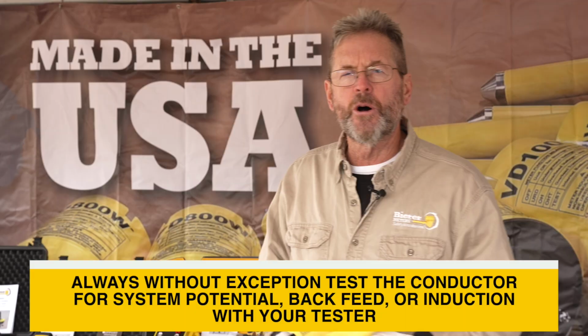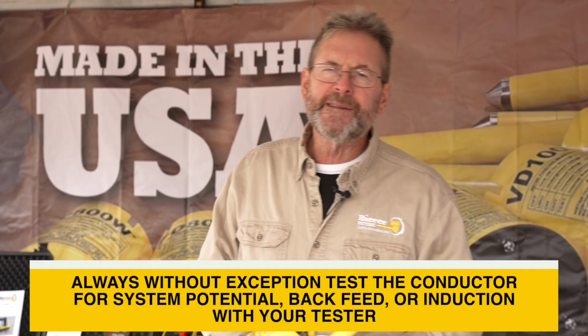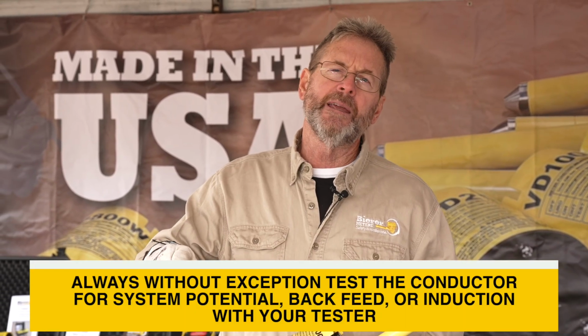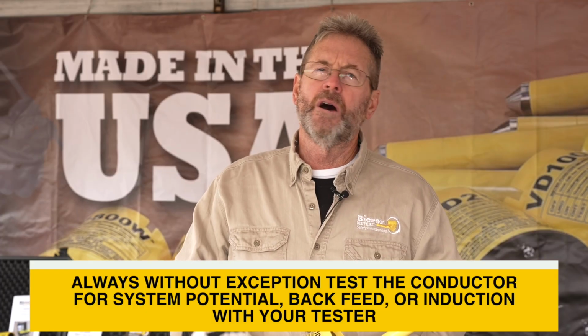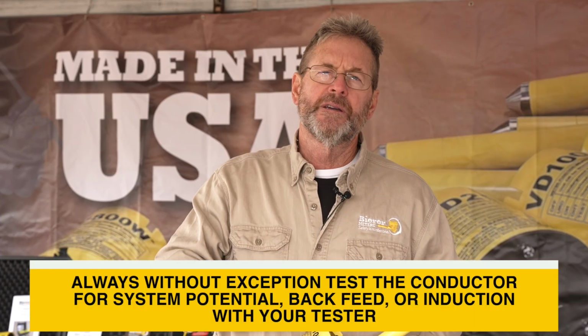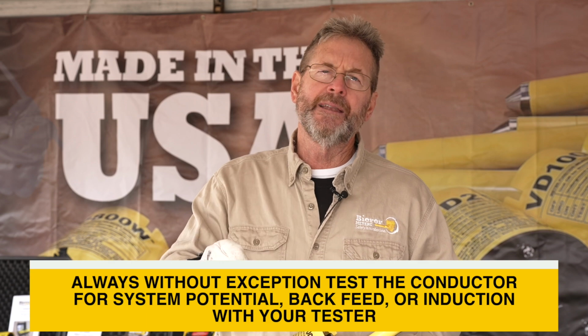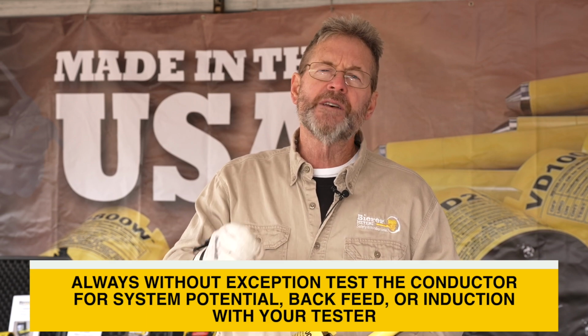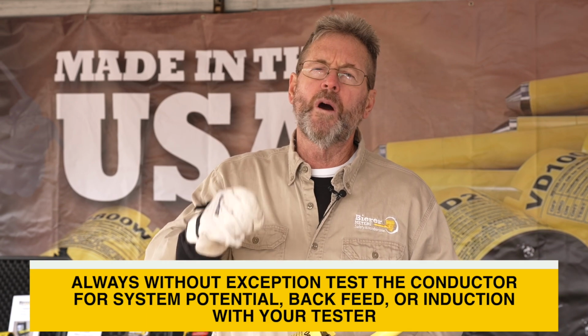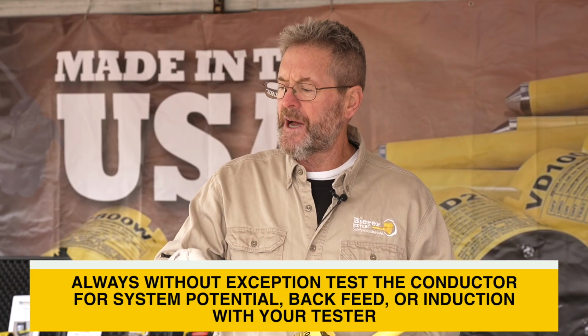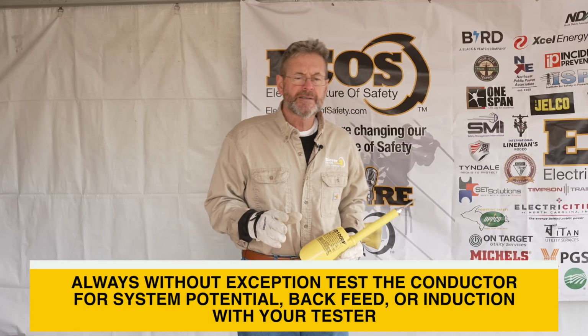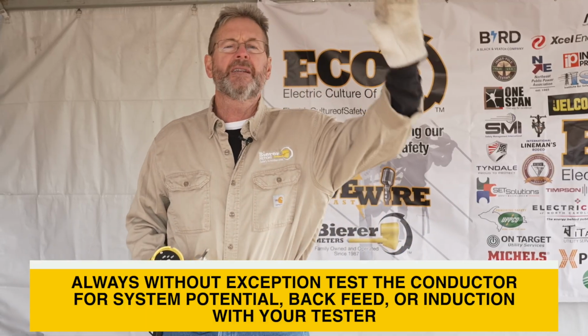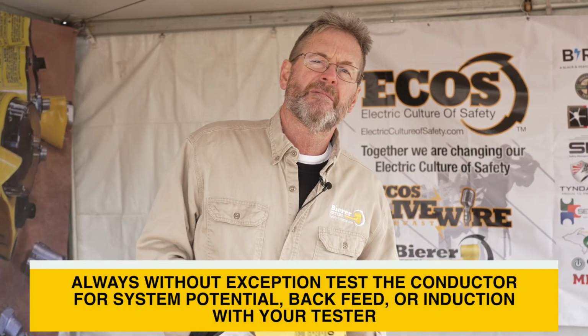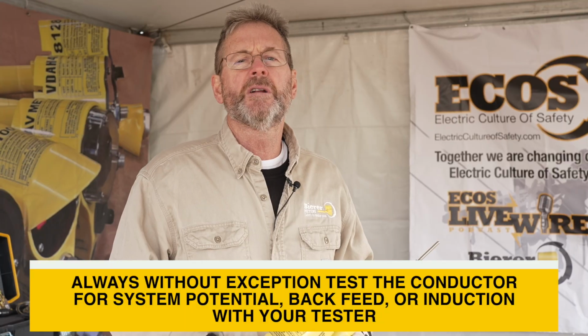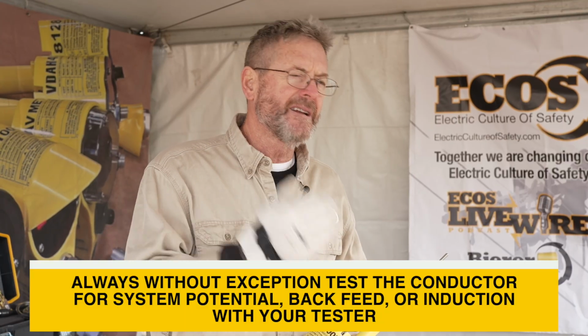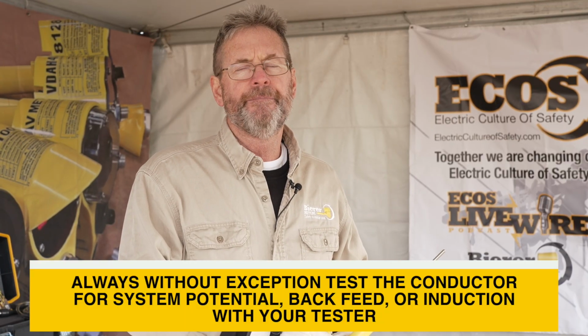Just because a switch is open, don't tell your line team to go ahead, it's good. No—we want you to test. Is there induction on that line that needs to be bled off? Is there backfeed? We always want you to test every single time. We do not want anybody saying 'oh it's good, I checked it, they called in, the switch is open, we're good.' Always test the conductor every single time.